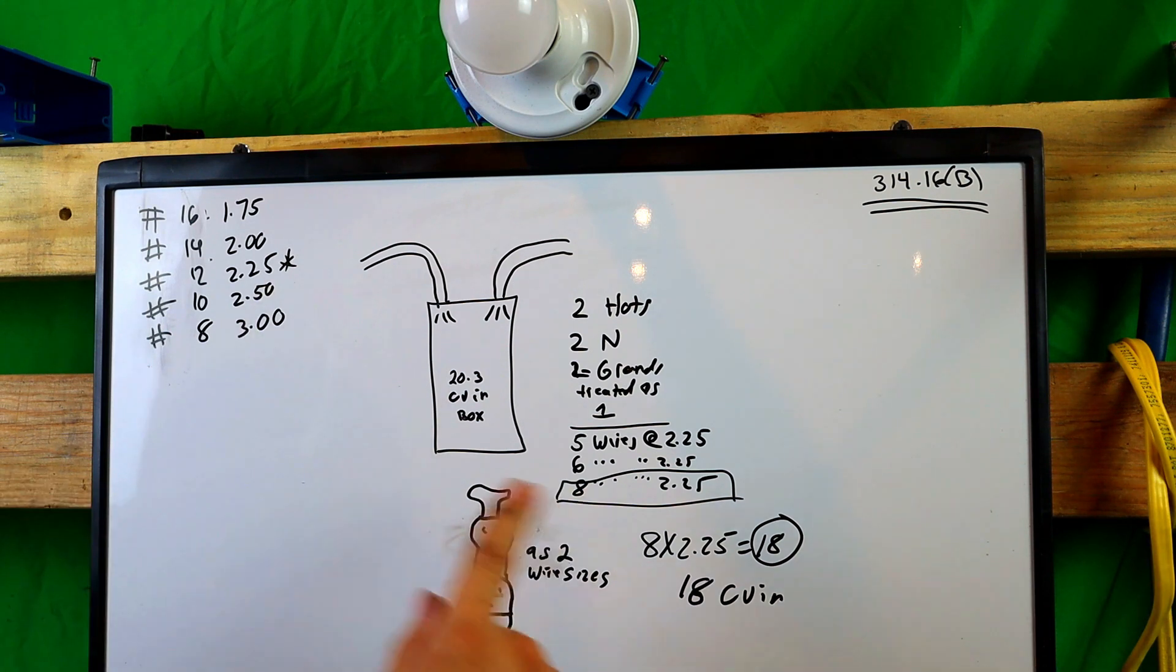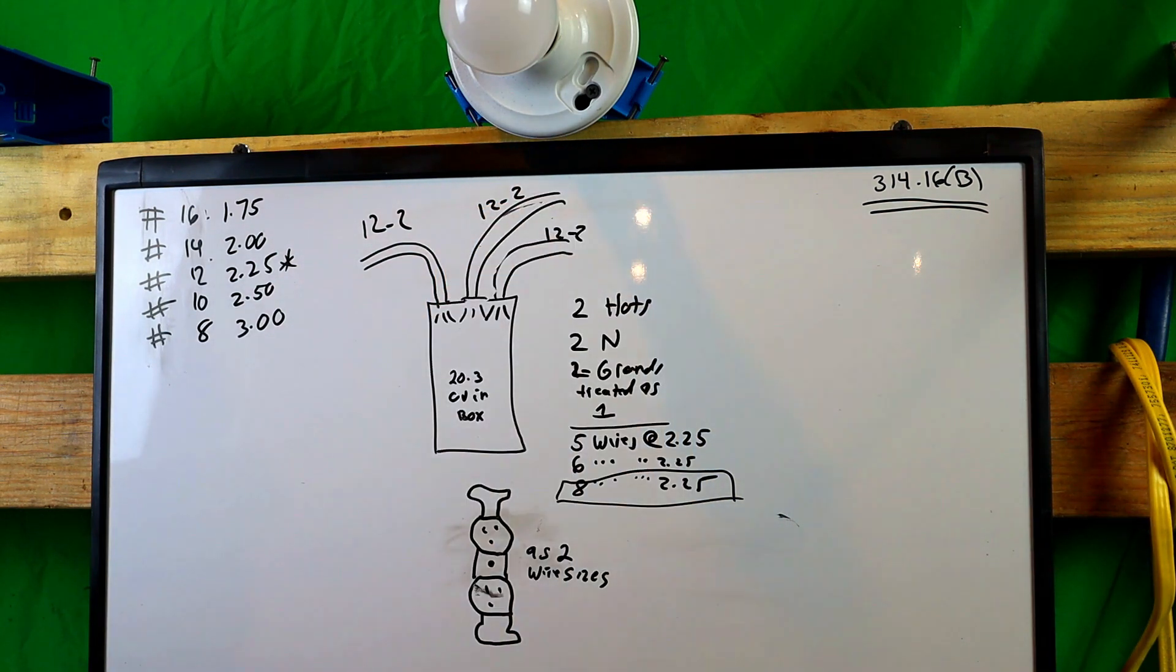Now let's take this one step further. We'll use the same box. Alright. We'll use this same setup here. We have one device. Let's go ahead and erase this. And let's assume we have another Romex cable coming out, all in 12 gauge. So this is 12-2, this is 12-2, and this is 12-2. Alright. Now, now we have one, two, three, four, five, six current carrying conductors.